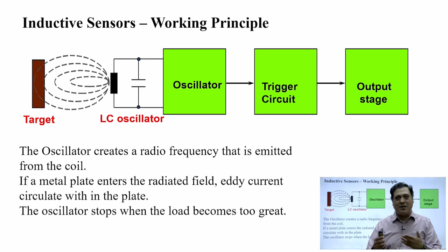Now, one of the most important factors is the sensing range of a sensor. How far an inductive sensor can sense a target is determined by a couple of factors. One of the most important factors is the size of the coil. The larger the size of the coil, the larger the sensing range. Why? Because when we have a larger coil, the electromagnetic field produced by the coil will be larger in size. When it is larger in size, we can sense a target from a larger distance. So, that is one of the major factors.